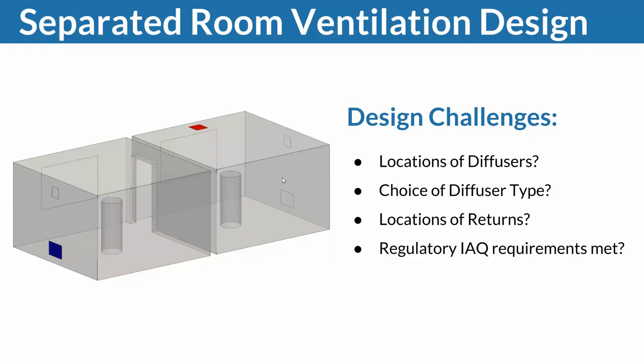First and foremost, where to put our diffusers to ensure enough supply of fresh air without draft risk or thermal comfort problems. What type of diffuser to choose, and where to put the returns. We're going to go through different scenarios — how the room looks with a displacement ventilation strategy, how it looks with a mixing strategy, and we also change the diffuser outlets and return location.